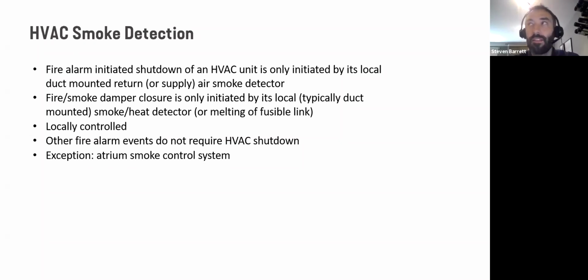So the key takeaway here is this local control idea. The smoke dampers have their own smoke detector. The unit itself by the fans has its own smoke detector. That's what shuts down the unit.